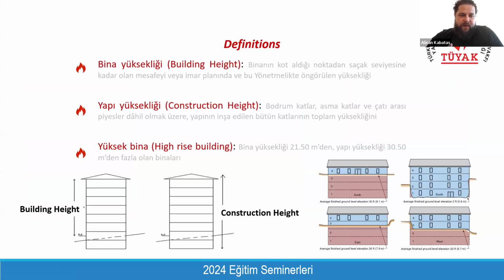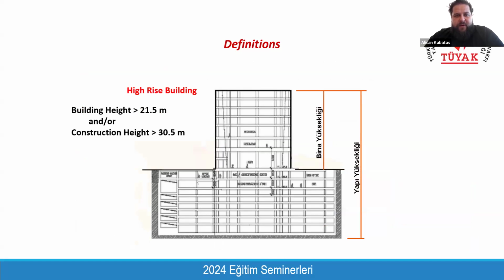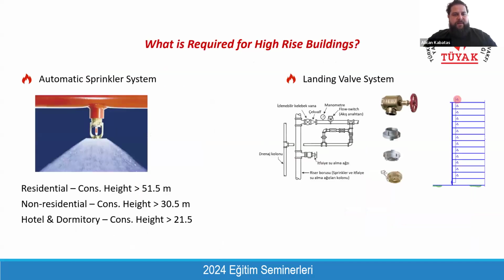Building height is measured from the ground level to the roof, and the construction height includes basement floors into the measurement. I would like to just summarize to remember what we are looking for during architectural design of the buildings. I will not focus on these issues. This is a sketch of the measurement of the building height. And when the building is high-rise, as per Turkish Fire Code, high-rise building means your building height is exceeding 21.5 meter, or the construction height is exceeding 30.5 meter.